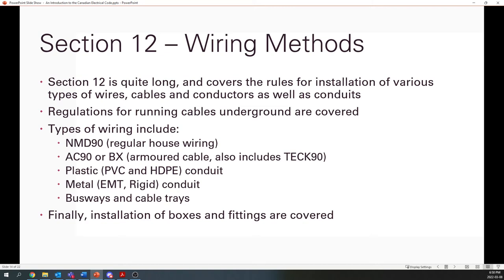I don't even know, it's like 50 pages long. So definitely a long one, definitely a lot of information in there. I'm not going to go really in depth at all there, but if you're using a certain type of wiring system or conduit, you're going to want to look in there to actually get the rules of how this has to be installed. And this applies a lot more to electricians, but if you're specifying sizes of conduits, sizes of wires, types of wires, how these different types of wires can be used, that's definitely there.